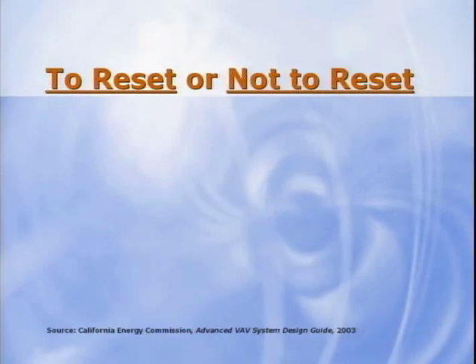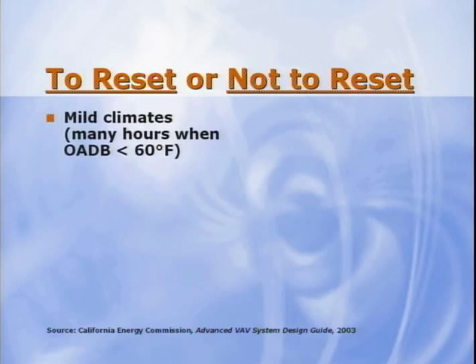This slide contains some general guidance on when and when not to use supply air reset. Conditions that favor using reset include mild climates that have many hours when the outdoor dry bulb temperature is below 60 degrees Fahrenheit. In this type of climate, the economizer-related benefits likely tip the scales in favor of supply air temperature reset.